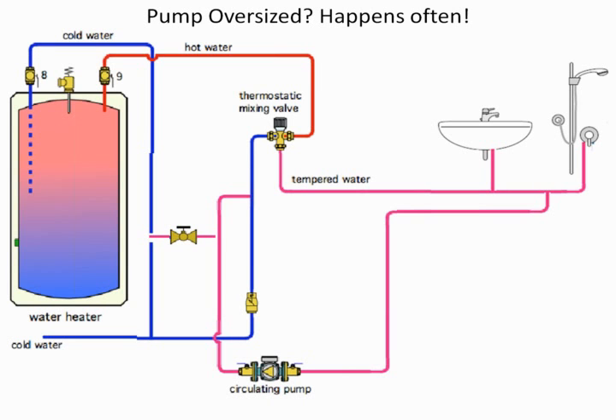It went to the pump guy, you know, the sales representative. He looked and he goes, they probably undersized it. Let me give them one horsepower pump. And all of a sudden, one horsepower pump got installed when a 1/24th was necessary. That might sound funny to you. That is an actual case that really did happen in installation. So what happens when that occurs?